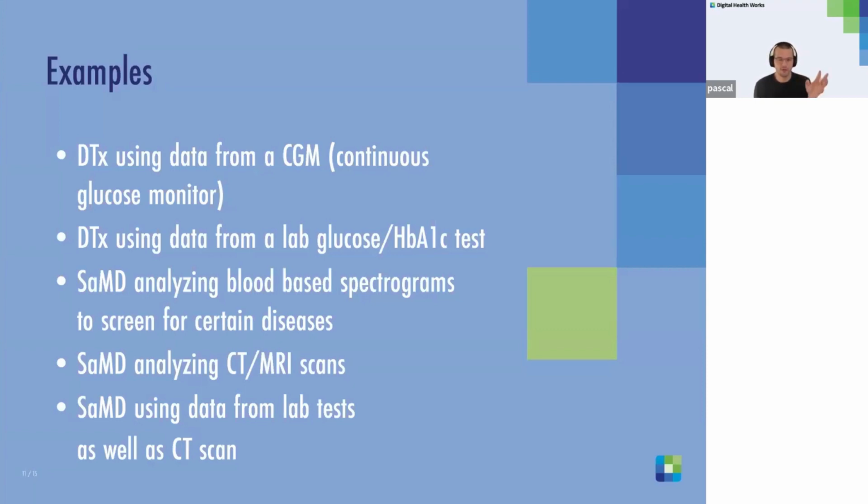So you want to know which one to fall under from the very beginning, because you'll reach out to a notified body fairly early in the process. First of all, you need to know which notified body you can reach out to. And even if you reach out to one that can do both, it's a completely different process or conformity assessment procedure within them. So you can't just say, oh, just kidding, we changed our mind, we want to do IVDR now. You need to know that from the very beginning, so you need to make an informed decision early on about that.